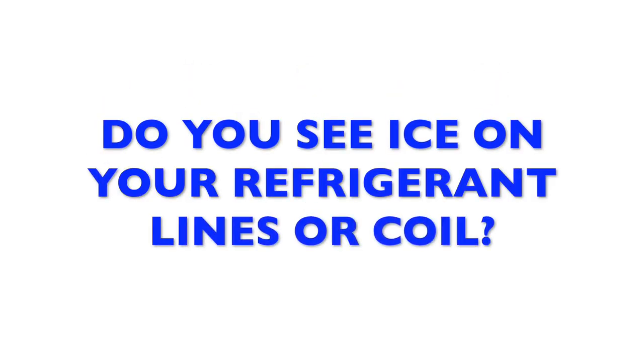And so when you think about an air conditioner with a coil operating at 32 degrees or maybe even a little below that, and you think of all the humidity in the air that we're taking out when running an air conditioner, that condensation that we normally run off to a floor drain is going to freeze onto the coil. And so it's a very common complaint: I see ice on a refrigerant line, or I can literally see ice on a coil.